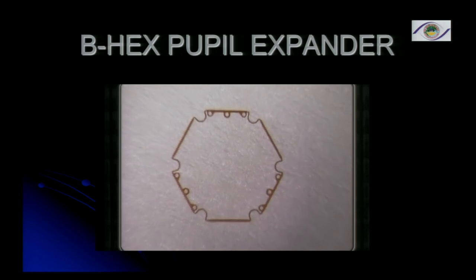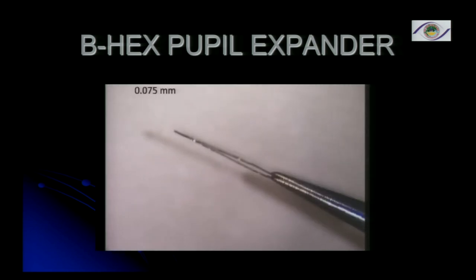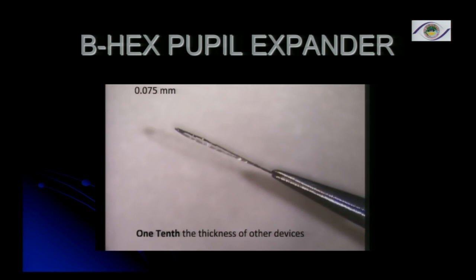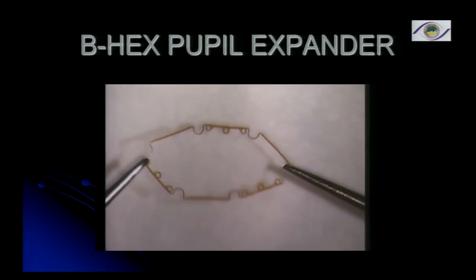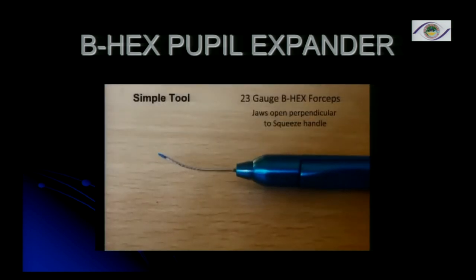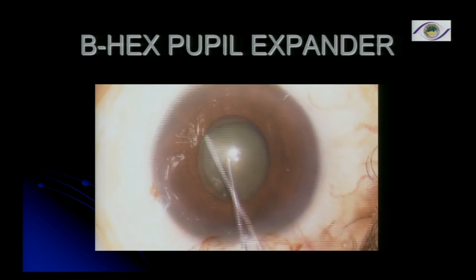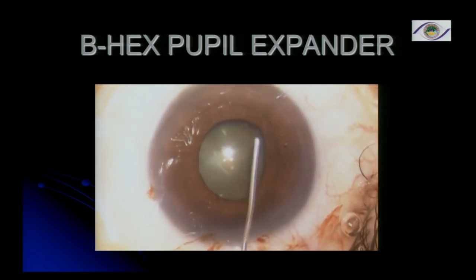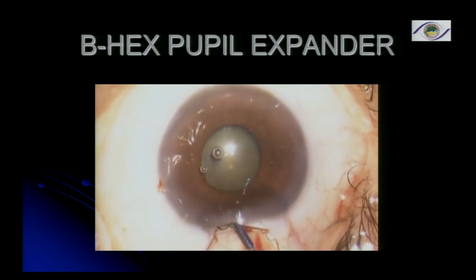The last video I'm going to show is the BHEX pupil expander, which is actually an Indian product. It's a very simple design with multiple tabs and flanges to hold the iris. It is very thin compared to the Malyugin ring — only 0.075 millimeters — extremely flexible, and gives you adequate pupil size to do any cataract surgery. You can use BHEX forceps to insert it through a side port. These are the advantages of the BHEX pupil expander compared to the Malyugin ring.